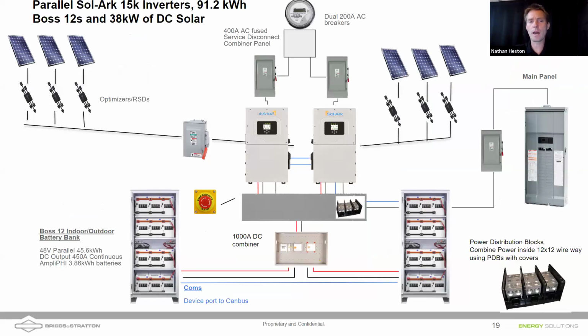Also showing this with our Boss 12 cabinets, your standard SimpliPHI battery, and a DC combiner. Keep in mind when combining battery banks, like two banks like this, or two of our 6.6 stacks, you want to combine those into a single bank before drawing power out of them. That ensures balanced power between all contributing batteries. You also want to make sure the cable lengths you choose when combining multiple battery banks into one are equal. Dissimilar cable lengths can reduce the overall load resistance on the battery bank with the shorter cable, causing it to do more work and decreasing overall lifetime.